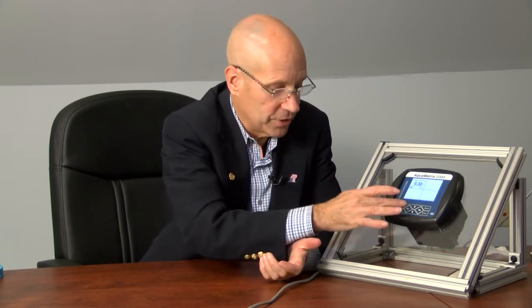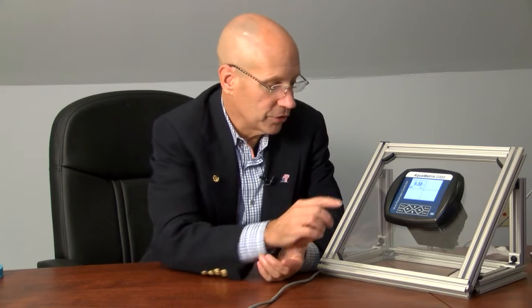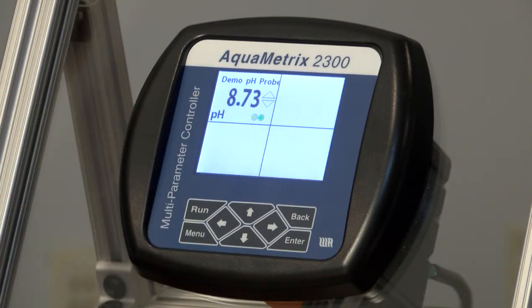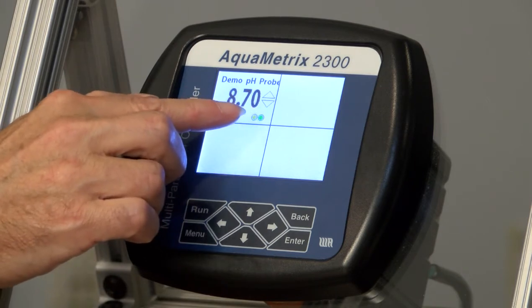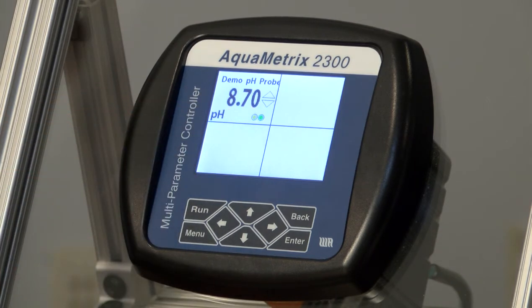The screen shows 4 sensors in one screen, although right now there's only one. If there are more than 4, then I press the down arrow to reveal them. Each of the quad screen shows 3 things: the process variable, in this case 8.73 pH, whether or not an alarm has been activated. Green light means that neither alarms or relays have been activated. A yellow light means that a relay has been activated, as it has here, and a red light means an alarm has been activated. We don't see one here. The up and down triangles show whether or not the process value is increasing or decreasing.